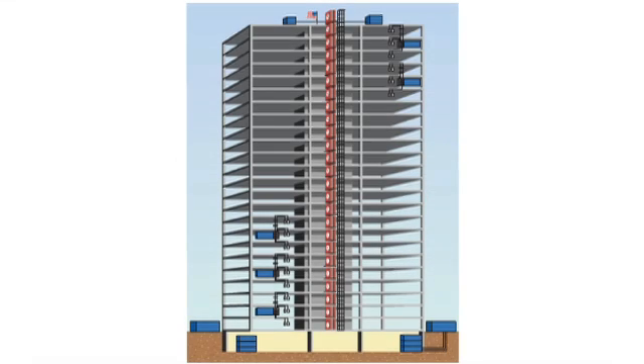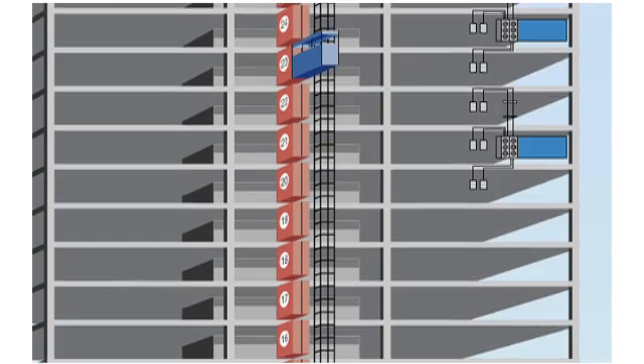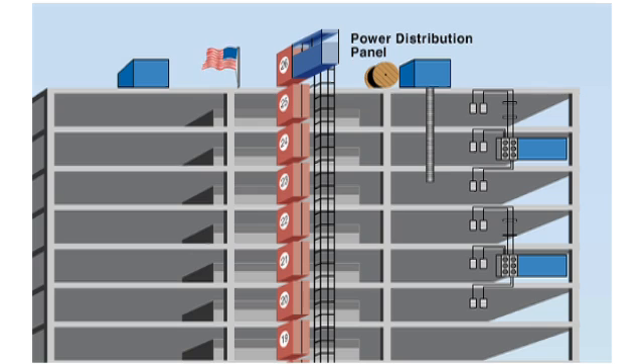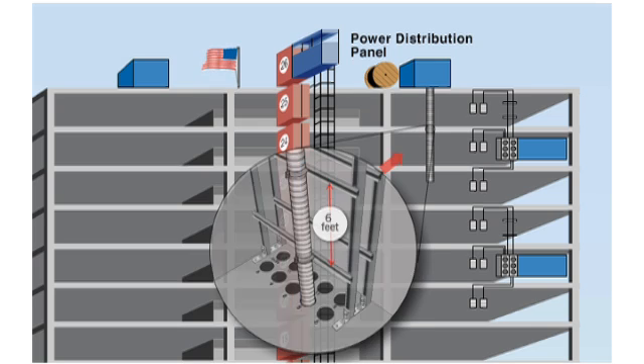Southwire provides installation instructions with each reel of riser MC cable stating that offsets or conductor supports of any type are not required. Now a contractor can install a vertical feeder from the basement all the way to the roof without having to worry about the additional time and cost of supporting the feeders inside the raceway.